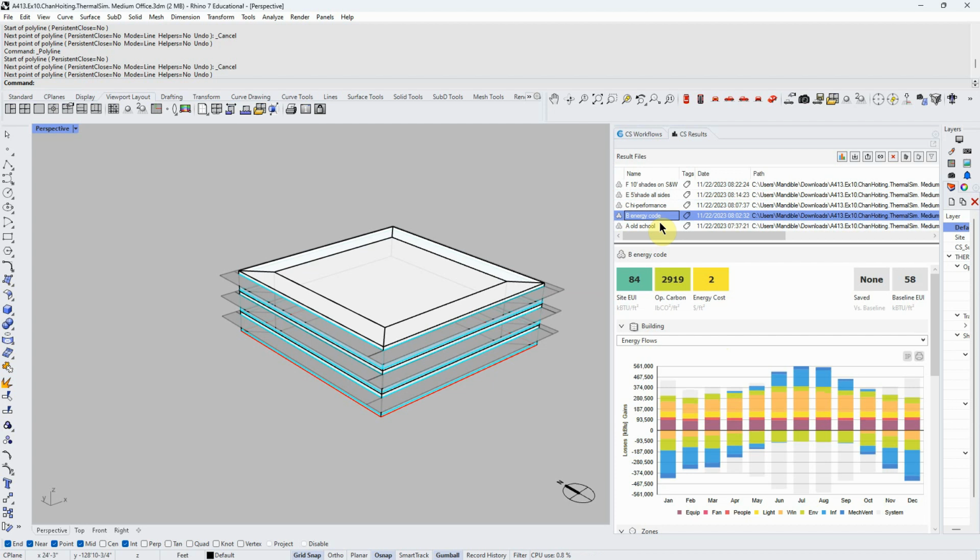Between the unshaded and the shaded, we're going to drop the gains in the summer a little bit, which is something we would want. At the same time, though, we're dropping the gains in the winter too, and we're actually getting some losses, because when we are shading the windows when it's cold outside, we're getting fewer gains, and we're also getting more losses, because there are more times when it's colder outside than inside, and the heat's going to move out through the windows. So what's happening here is that we're balancing out the advantage of shading in the summer against the disadvantage of shading the windows in the winter.